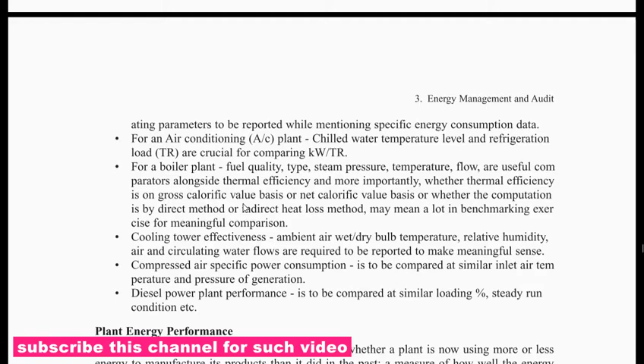For air conditioning, chilled water temperature level and refrigeration load are crucial for comparing kilowatt per ton. For the boiler plant, fuel quality and type, steam pressure, temperature, and flow are useful comparators alongside thermal efficiency. More importantly, whether the thermal efficiency is on a gross calorific value basis or net calorific value basis, and whether it is computed by the direct method or indirect heat loss method, may mean a lot for a meaningful benchmarking comparison.